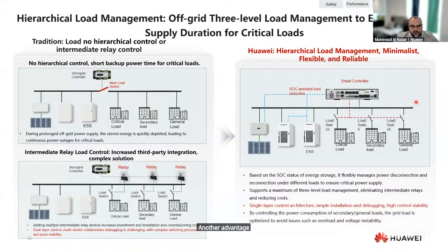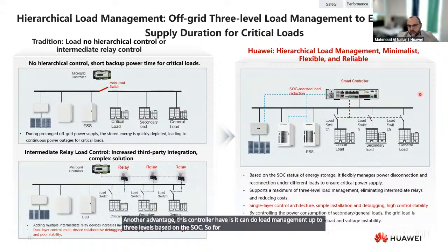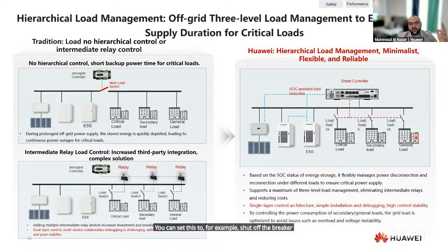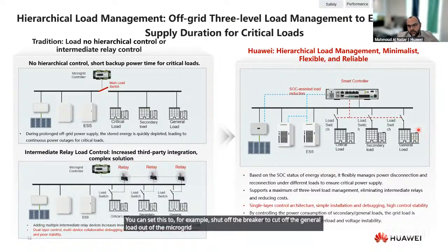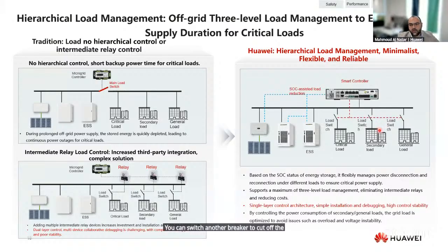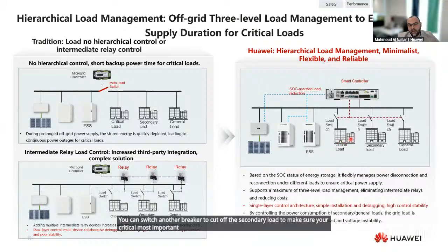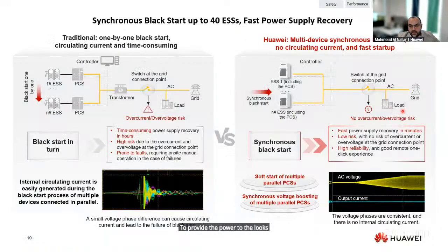Another advantage this controller has is that it can do load management up to 3 levels based on the SOC. So, for example, if your SOC reaches 50%, you can set this to shut off the breaker to cut off the general load, or the backup load, out of the microgrid. Then, if your SOC, state of charge, reaches 20%, you can switch another breaker to cut off, let's say, the secondary load, to make sure your critical, most important loads still have power until the power or the solar generation is resumed, or the diesel generator is back to provide power to the loads.